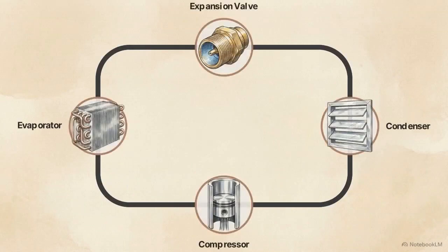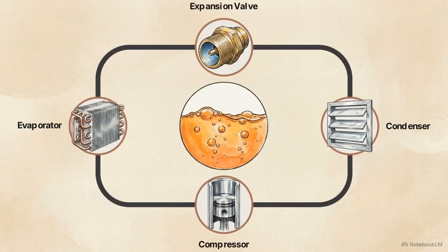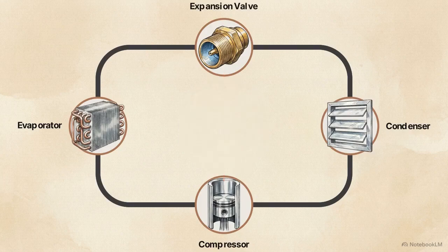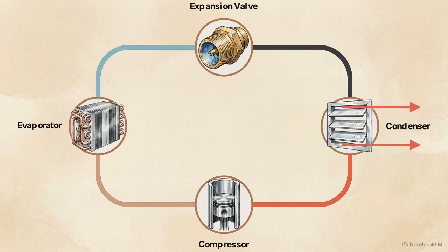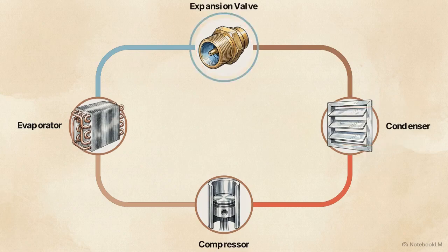This animation shows a closed-loop pipe system, demonstrating the single rule of physics that makes mechanical cooling possible: phase change. This is the scientific principle where a liquid absorbs a massive amount of heat energy from its surroundings as it boils and turns into gas. The liquid is forced through a tiny nozzle. This instantly drops the pressure, turning the refrigerant icy cold again, ready to reset the loop.